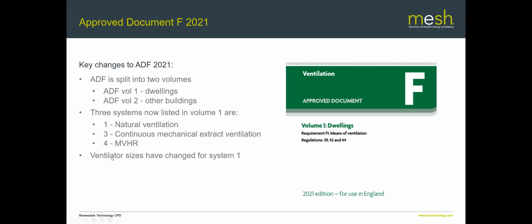And you'll be pleased to know that ventilation sizes have changed for System 1 from the 2010 version. And the ventilation rates for all 3 systems, 1, 3, and 4, have been updated. The system that's been removed, which was System 2, is for passive stack. So passive stack is no longer mentioned in Approved Document F, Volume 1. So that's gone.